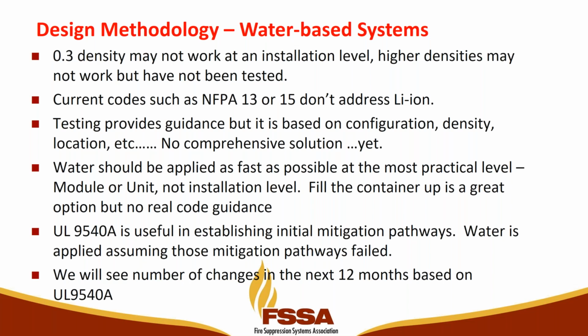Instead of giving you a density, what they did was come back and say, let's provide separation. So instead of being able to put racks right next to each other for certain types of batteries, you need 9 feet of separation. Now, that's not really going to happen in the world. Utilities and developers are all trying to pack as many batteries as close as they can inside a container. So it's going to be interesting to see how that plays out. But none of the codes are really set up to address this. NFPA 13 and 15 don't really give you good guidance on lithium-ion.